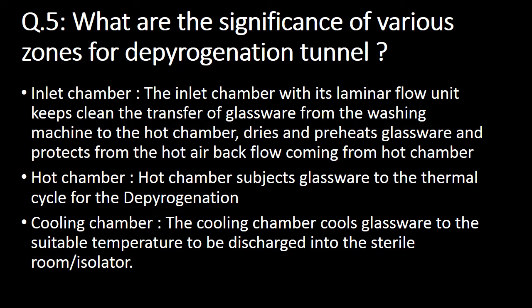Fifth important question: what is the significance of various zones of the depyrogenation tunnel? The first zone is the inlet chamber. The inlet chamber with its laminar flow unit keeps clean the transfer of glassware from the washing machine to the hot chamber. It dries and preheats glassware and protects from the hot air coming back from the hot chamber. The next zone is the hot chamber, which subjects glassware to the thermal cycle for depyrogenation. The third zone is the cooling chamber, which cools the glassware to a suitable temperature to be discharged into the sterile room or isolator.